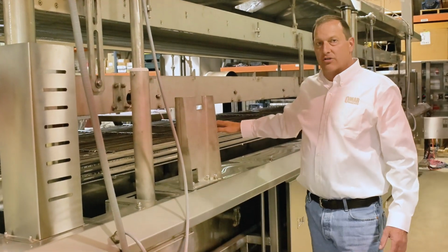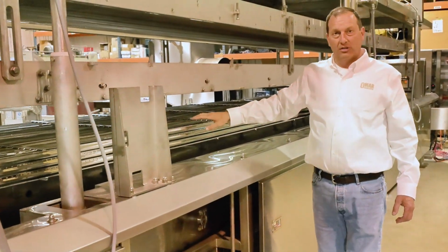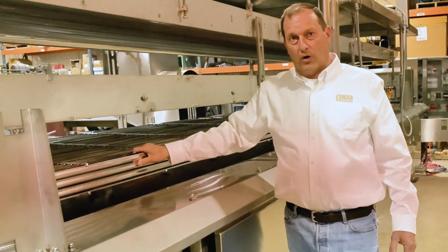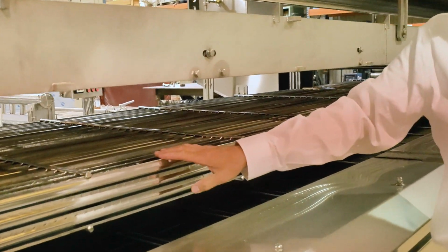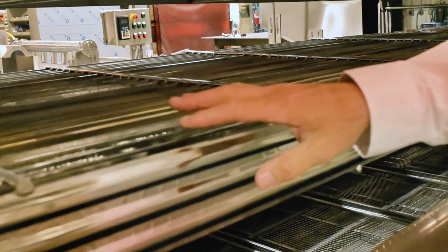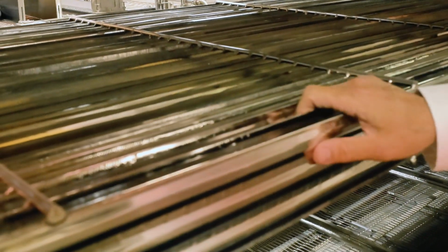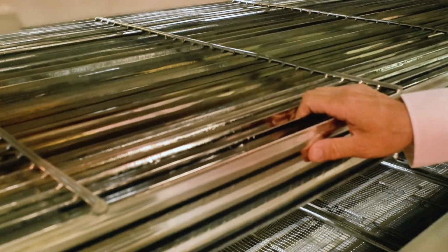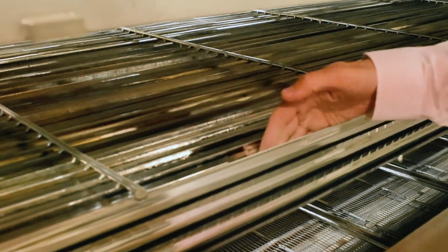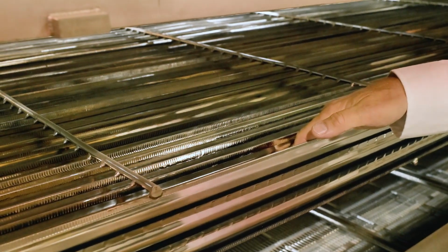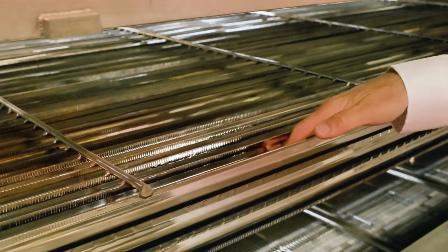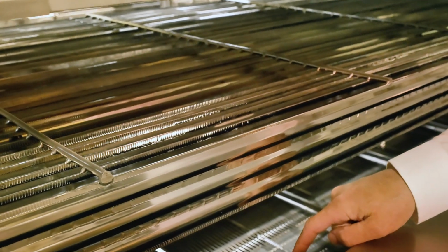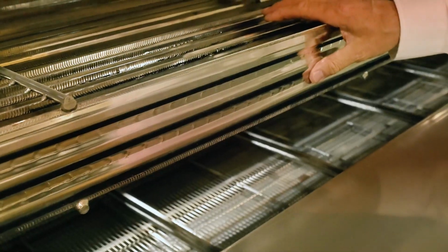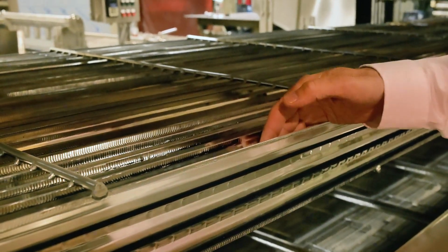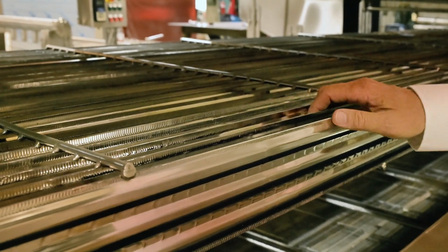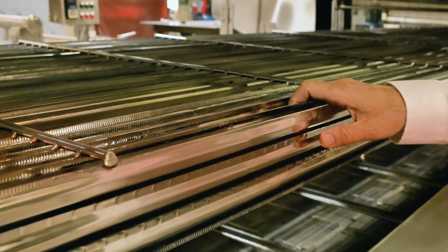The heat exchanger is an electropolished ASME stamped weldment. This heat exchanger has a larger gap between the plates than competitive concepts. That results in better sediment transfer through the heat exchanger to make sure the sediment gets down into the sediment conveyor. Larger surface area, greater spacing equates to a better heat transfer than competitive designs.